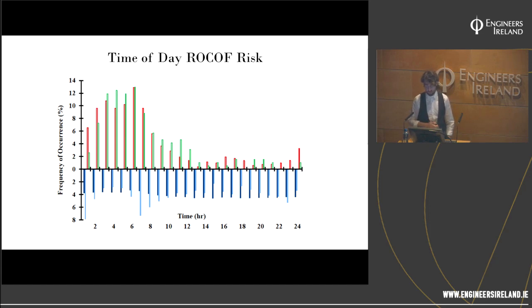Now, if you contrast that with over-frequency events for loss of interconnector, we can see that the risk is much higher during the nighttime, because that's when we export. We start importing during the day, and this risk falls off. So there's an asymmetry here: we need to guard against different things at different times.